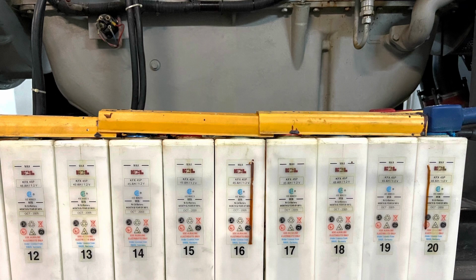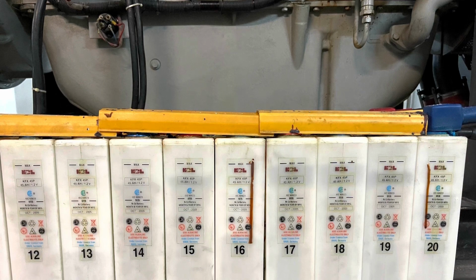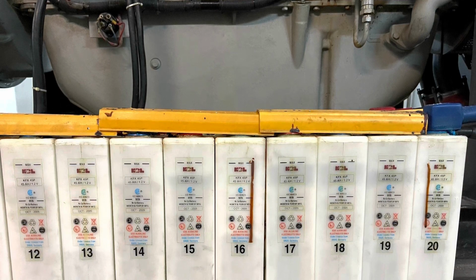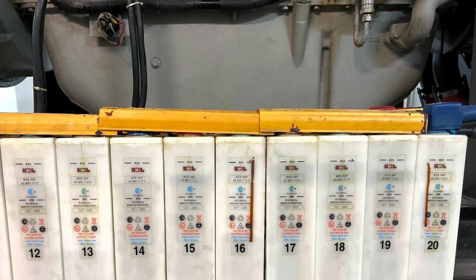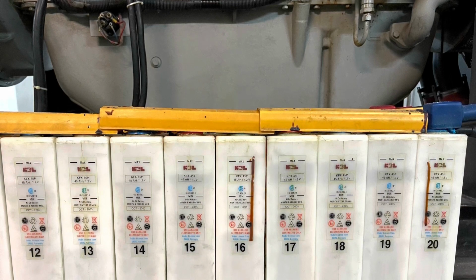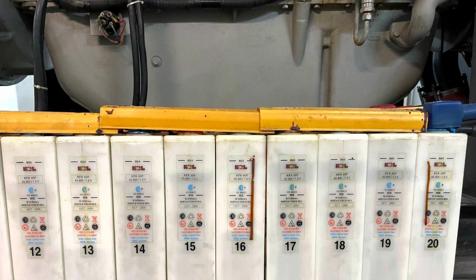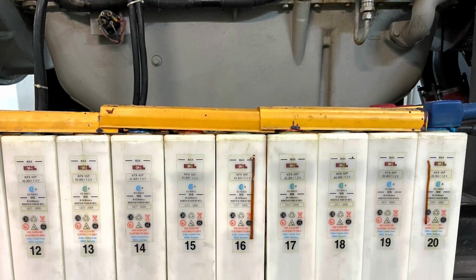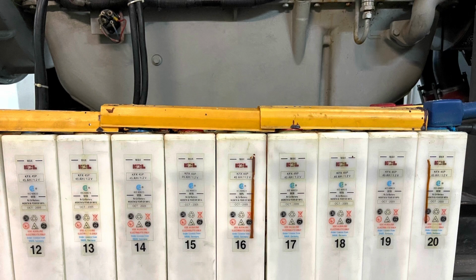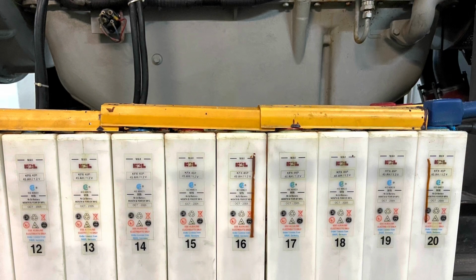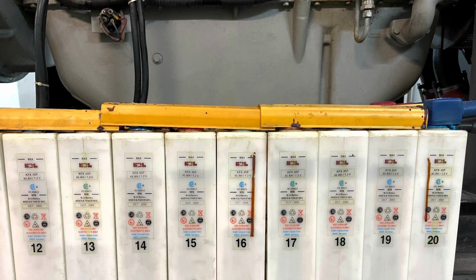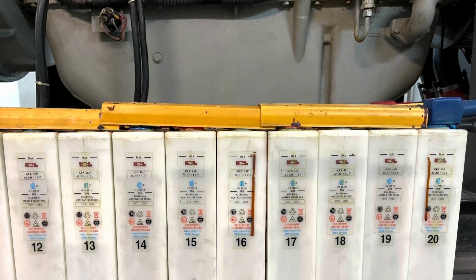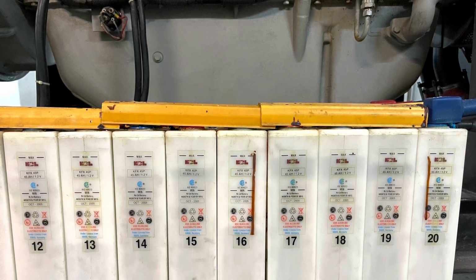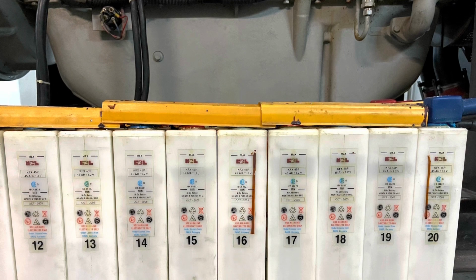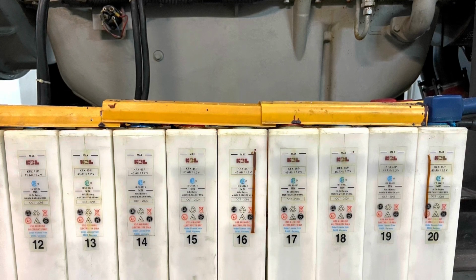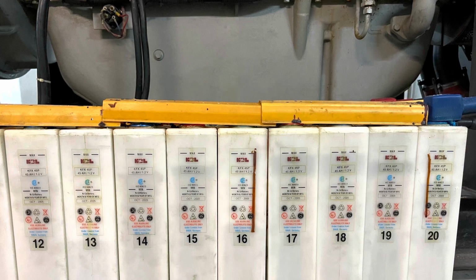So either way, if you're asking me what the lifespan of a nickel cadmium battery is, my best advice is to test the condition or strength of your battery during the cranking. Witness the voltage drop. This should be a more accurate way, because each genset model is different, and each genset starter is different.